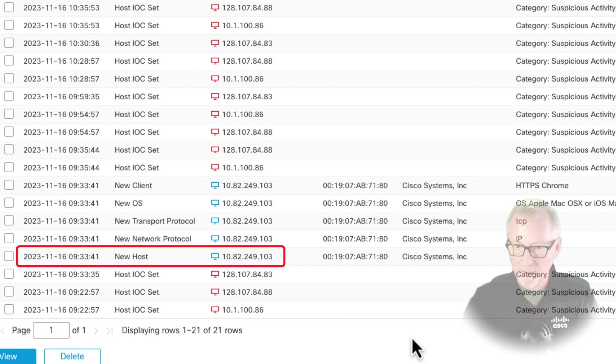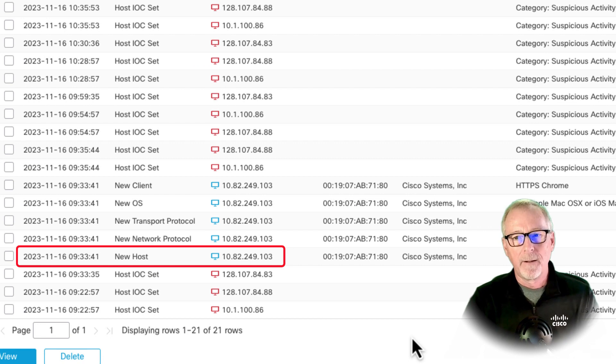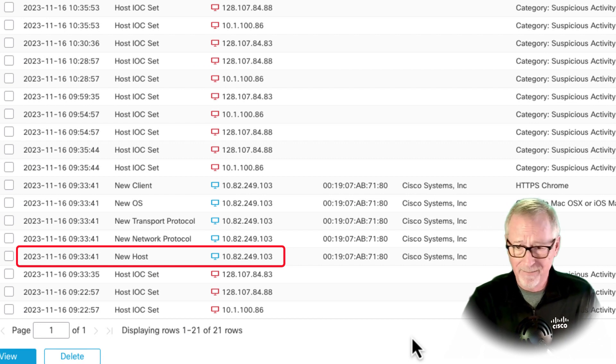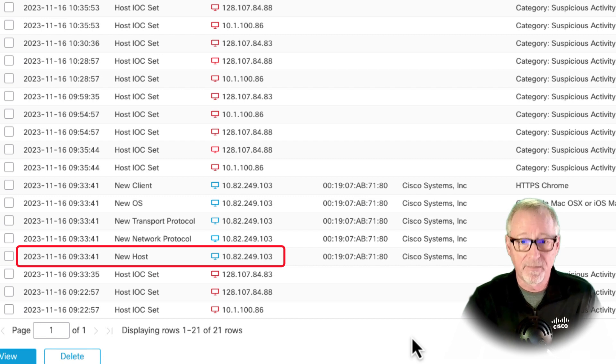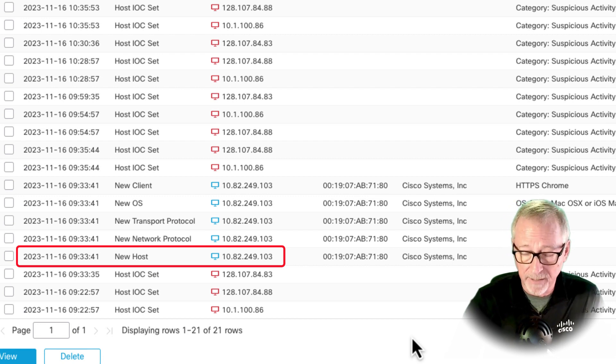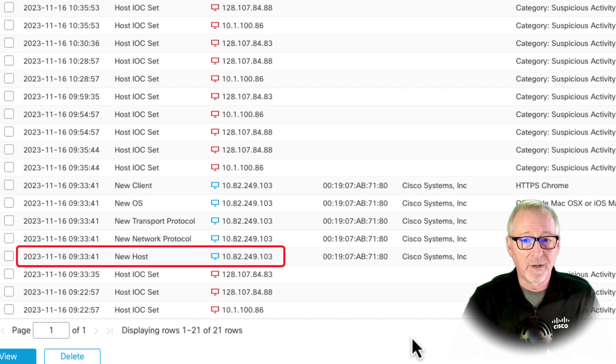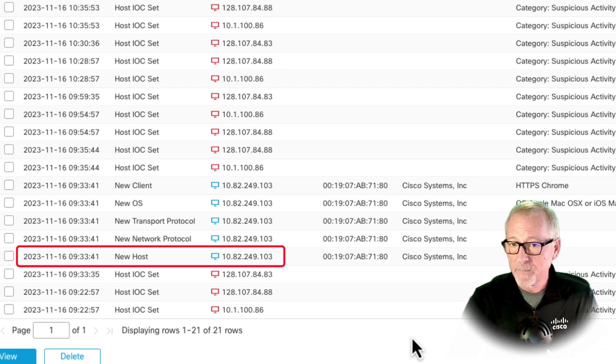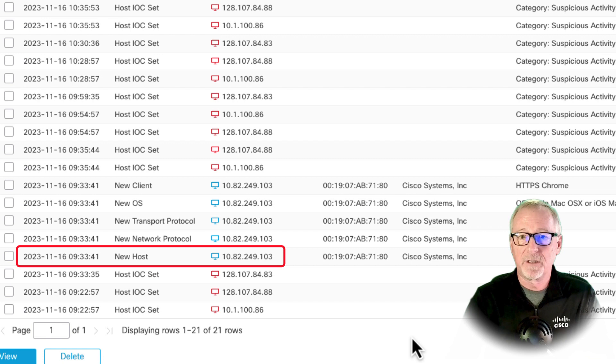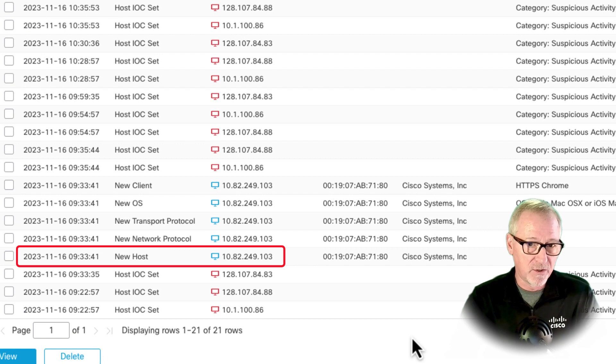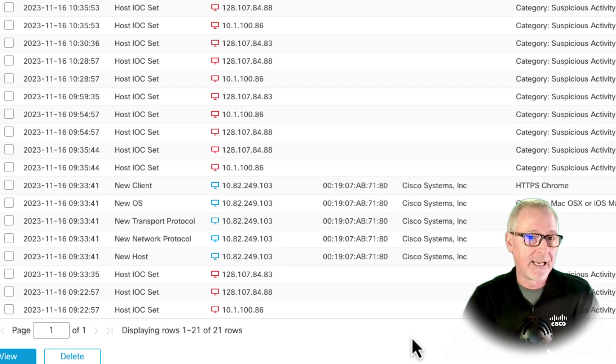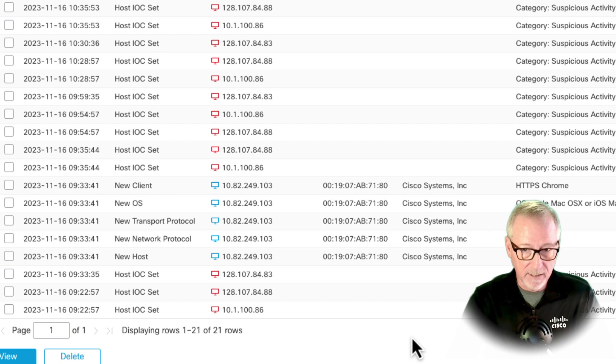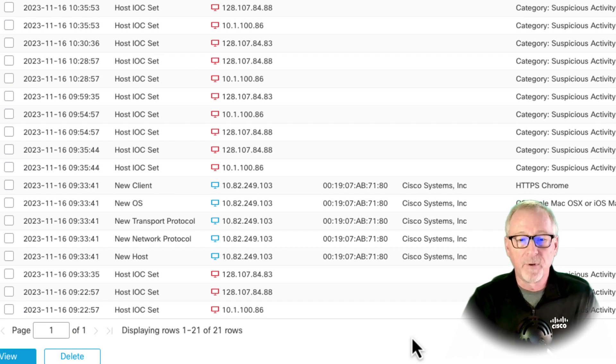So new host is a new host discovered on the network. You have a host database that's been built for all the hosts that we can see with the passive detection on our devices out there. And so we know what IPs we've seen. So as soon as it sees a communication from an IP it hasn't seen before, it generates this new host event. So that means a new host I haven't seen before, it just showed up on the network. Again, control network, static network. Sure, they add hosts to them from time to time, but rarely. You don't add a host every day, every week, every month, probably to a control network. So when a new host comes on the network, it might be something you might be interested in.